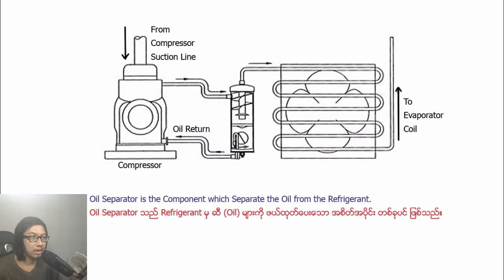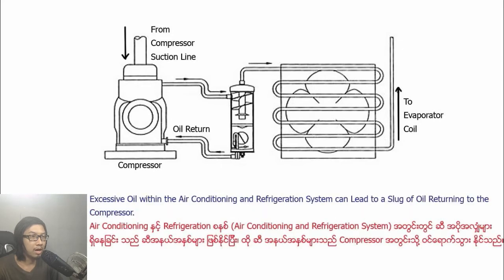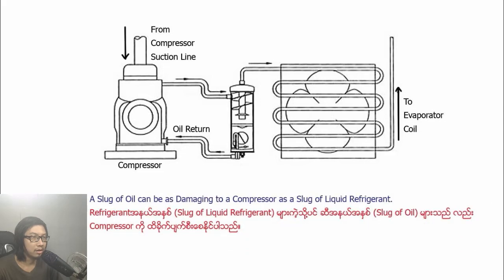An oil separator is the component which separates the oil from the refrigerant. Excessive oil within the air conditioning and refrigeration system can lead to a slug of oil returning to the compressor. A slug of oil can be as damaging to a compressor as a slug of liquid refrigerant.